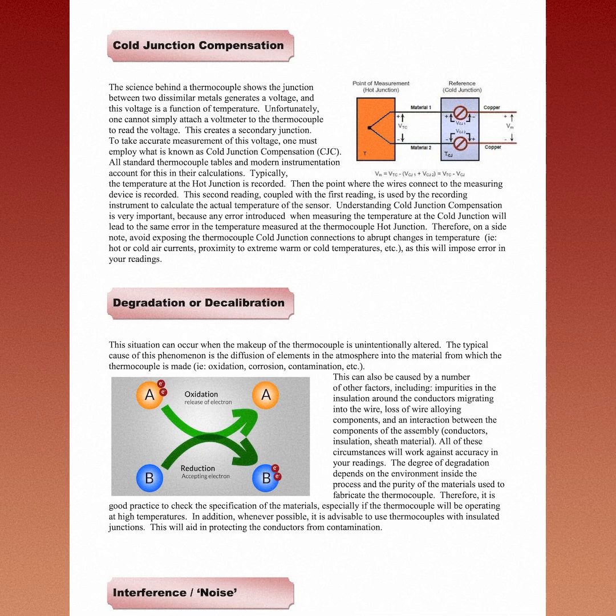The degree of degradation depends on the environment inside the process and the purity of the materials used to fabricate the thermocouple. Therefore, it is good practice to check the specification of the materials, especially if the thermocouple will be operating at high temperatures. In addition, whenever possible, it is advisable to use thermocouples with insulated junctions. This will aid in protecting the conductors from contamination.